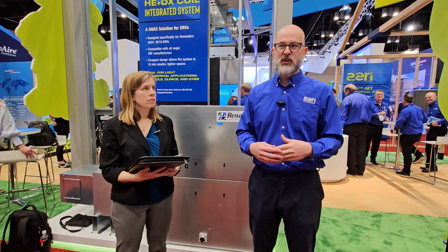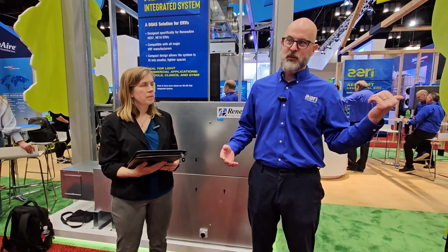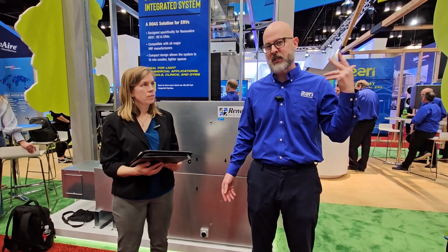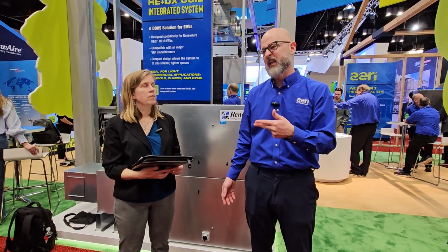So you have belts, you have motors, you have VFDs, you've got controls, and seals. So you have a lot of potential failure points. Versus with a RenewAire product, with our plate heat exchanger, it literally sits there. And so, maintenance people might not always be on the top of their game. They might just leave the unit for years, never open the door. And so if you got a wheel or something like that, you got a problem. Because what if the belt breaks? Then, as I talked about before, you're just bringing all of that unconditioned air from outside straight into your building. And effectively, you don't have a heat exchanger at that point.